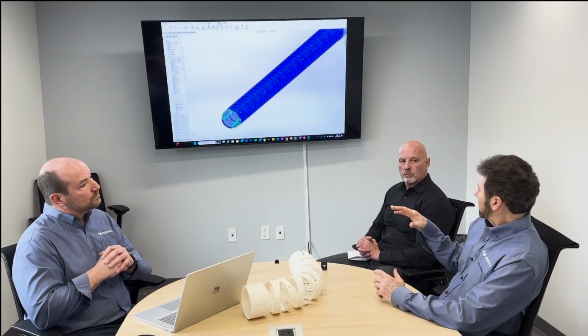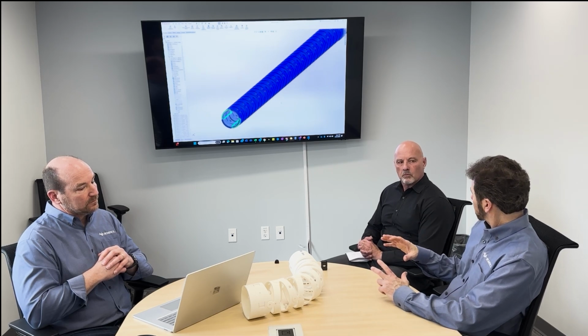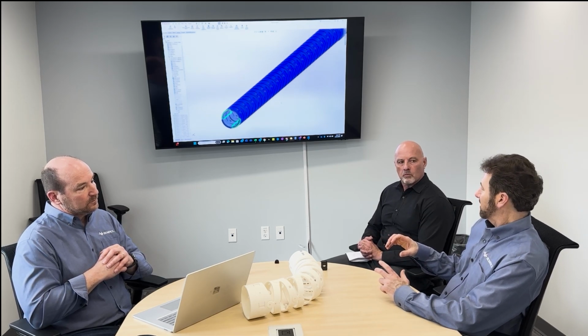And with this design, we can make it bigger, we can make it smaller, we can use different hypotube sizes, we can make different angles that it can articulate through. We have a way of manufacturing it so that when we do weld it together, we can pin each part, and that also lends itself to high production automated manufacture. We could feed these into a bowl and have them all put together and welded together, make sections as long as we want, as small as we want.